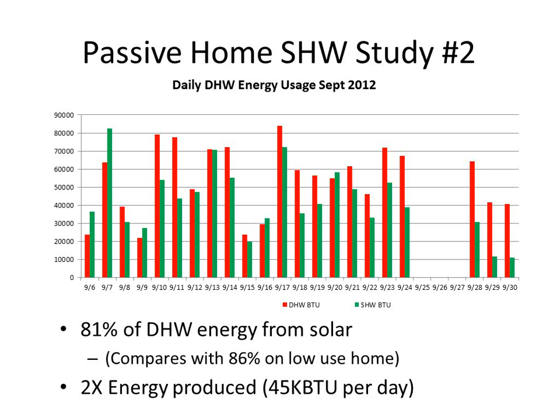In the same month, the house next door got 86% of its energy from the system. Looking at the scale, we're producing on sunny days generally 40 to 60,000 BTUs of energy on that system. The nameplate rating on the collectors is 30,000 BTUs per day, so they're producing nameplate rating on most sunny days. The system next door was producing anywhere from 15 to 20,000 BTUs per day.